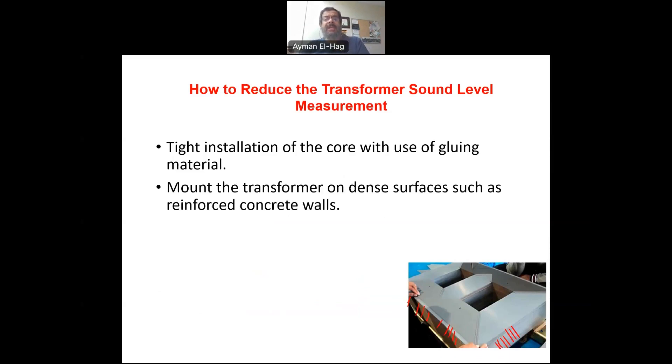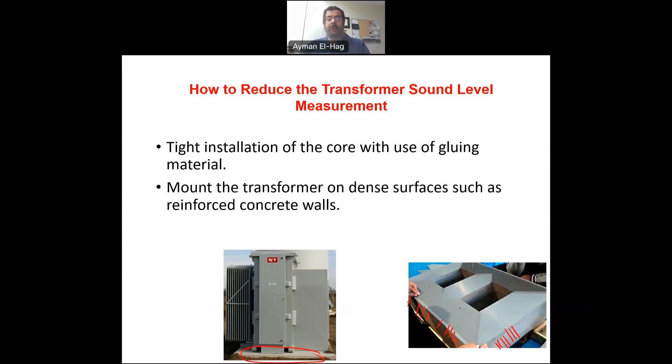Another way is when you install the transformer, you install it on a dense surface like a reinforced concrete wall like this one here. Now when you install the transformer on such a dense surface it will absorb part of this noise and it will not be amplified. Also you can use some acoustical damping material in the transformer, inside the transformer, outside the transformer so that it can absorb and minimize the level of noise. So these are some basic information about the transformer sound level. It comes from where, how we measure it, and finally how we can minimize it.